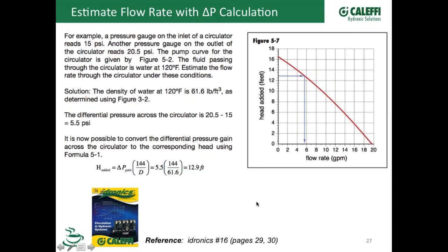Let's say we put gauges on both sides of the pump, and we saw a pressure differential of 20.5 pounds on the outlet side, 15 on the inlet. So we've got a DP, pressure differential, of 5.5 pounds. You can put that into the formula here, and you need to know the temperature of the water, because it makes a little bit of an effect. So if you can nail that down, get that number real accurate, put it in there, and in this case we've got 12.9 feet of head being developed.